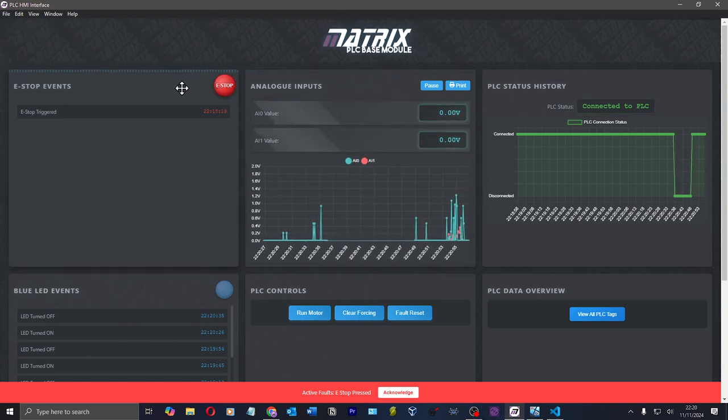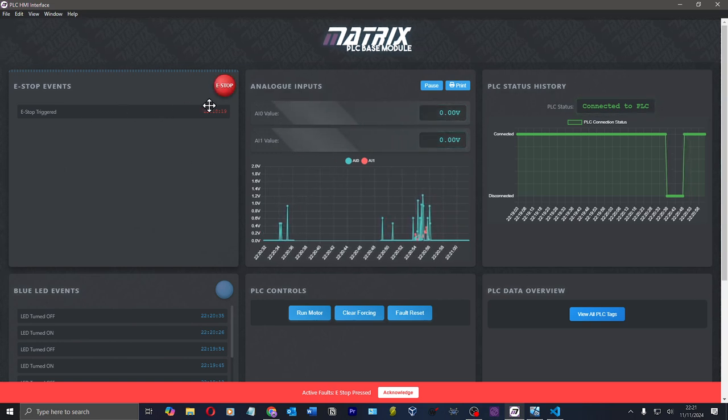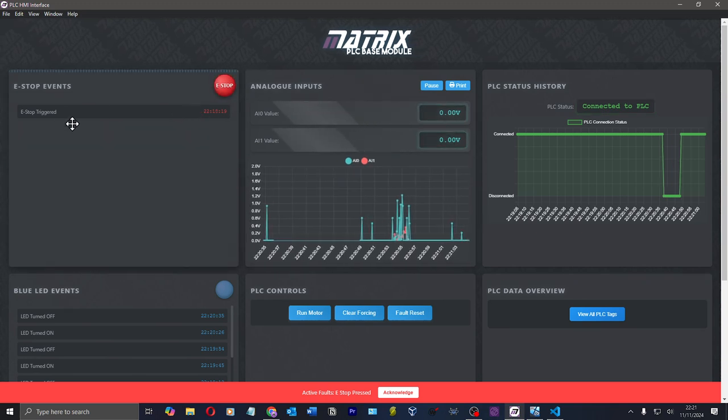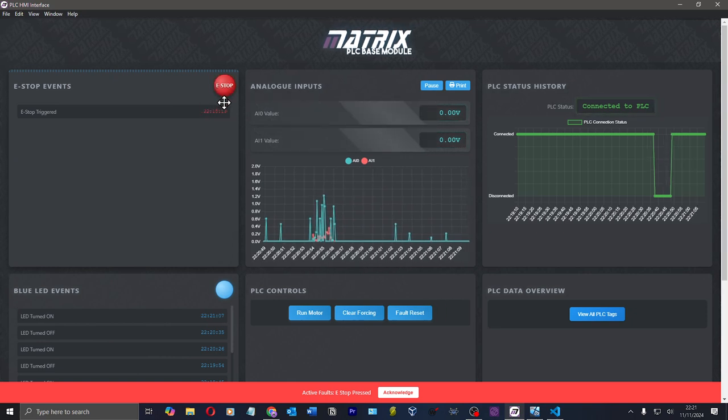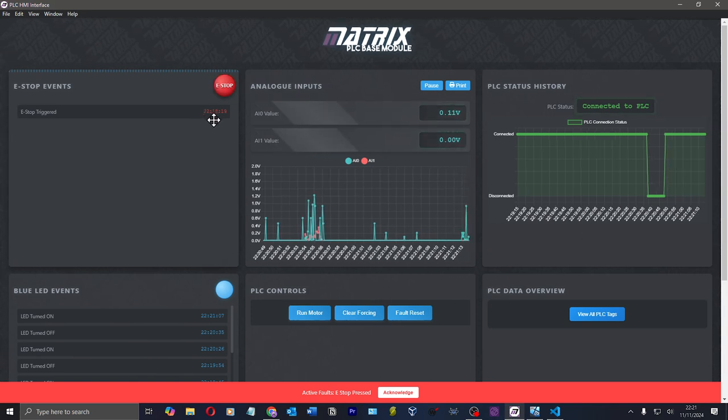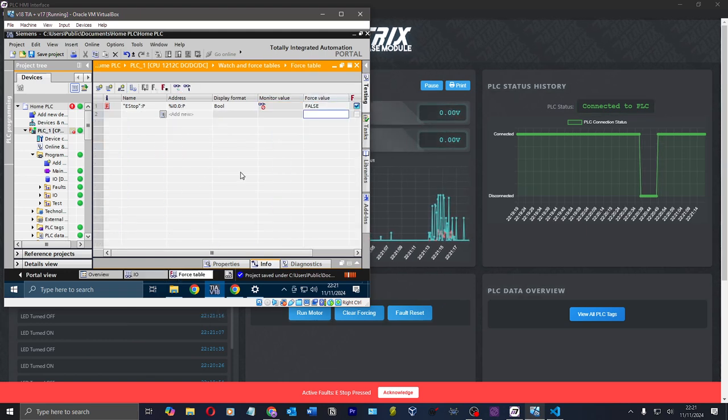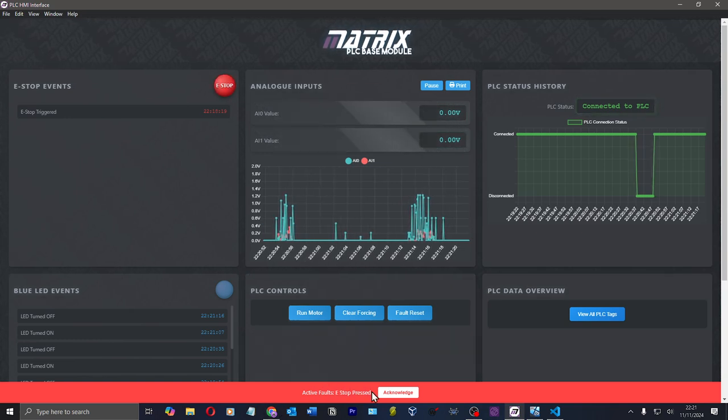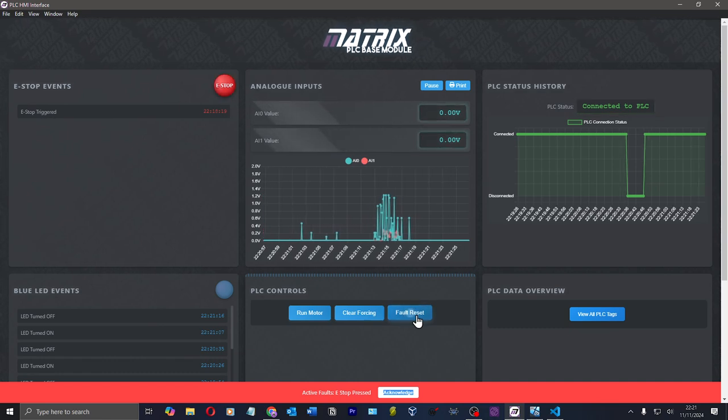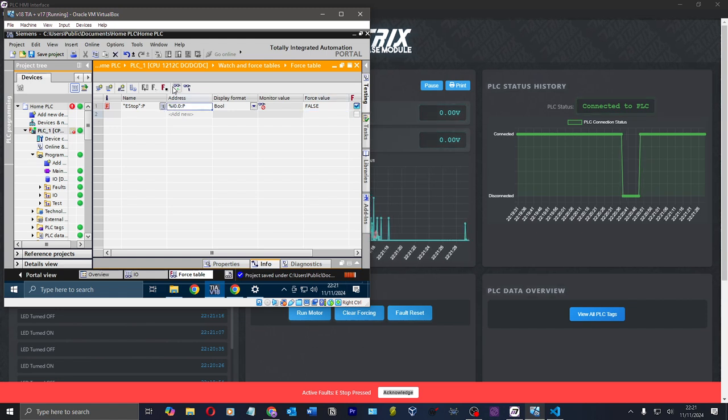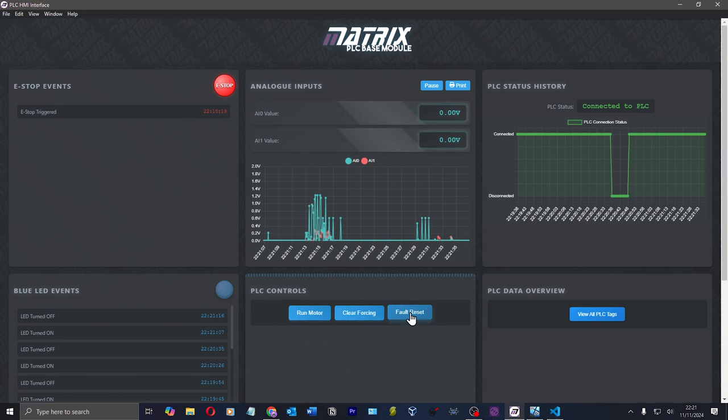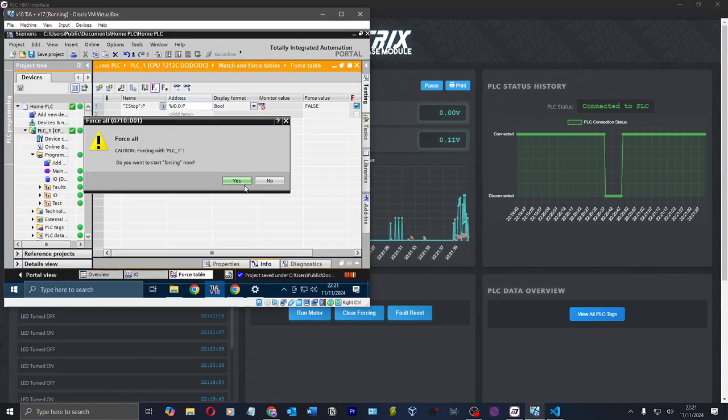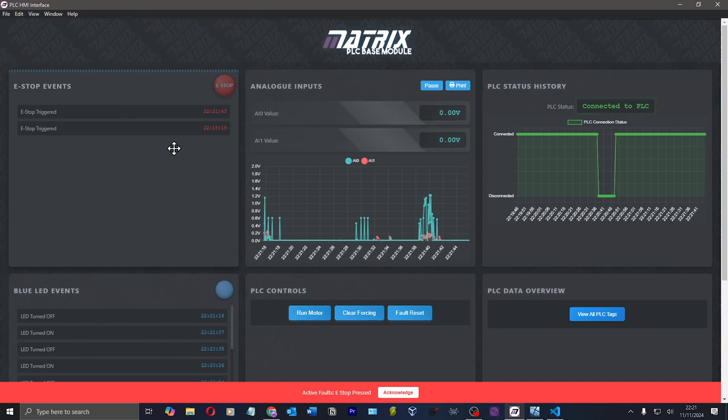I've got an e-stop wired into my PLC. At the moment I'm forcing it off. Because I'm forcing the e-stop off, this e-stop circle here is flashing and it tells me when that happened. At the bottom here, I've got a banner here that says active faults, e-stop pressed. If I click acknowledge, nothing happens. If I click fault reset, nothing happens. If I go back to TIA and I stop forcing, then that e-stop event, fault reset and now my e-stop's gone.